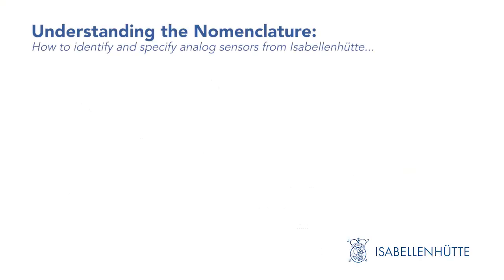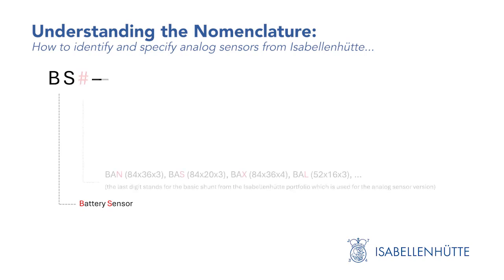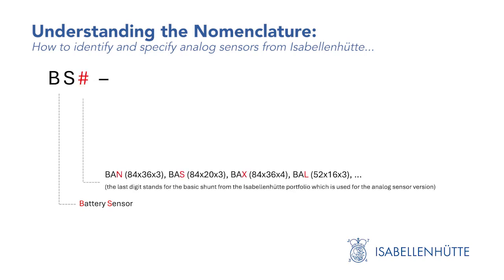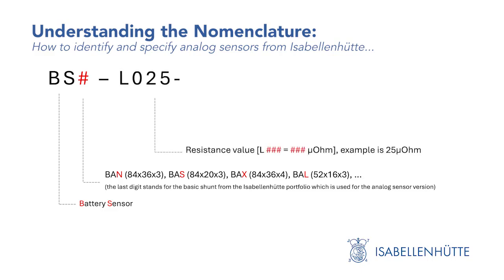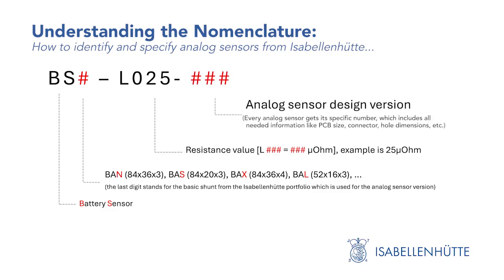The nomenclature of our sensors is relatively simple. The first two letters stand for the words battery sensor, and the third letter indicates the shunt's basic design. So a sensor based on the BAS shunt, a common example, would be called BSS. The following digits show the resistance value in microohms, and the L highlights the low ohmic nature of our products. The last three digits indicate the product version number, typically indicating different PCB configurations as well as different shunt dimensions such as hole spacing, hole diameter, or a special coating of the shunt.